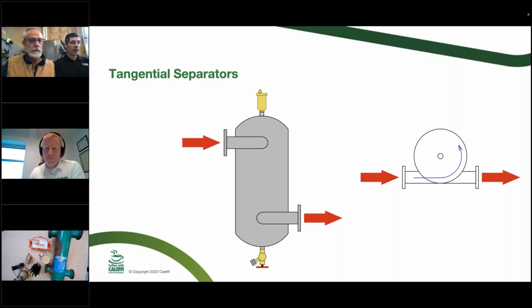So another category in commercial systems, generally big flange systems, would be a tangential separator. This is something that works really well to separate the flow as it goes through. It kind of goes through in a big vortex, and it's going to bring the air to the center and right up to the top. The caveat is that it needs a very specific flow rate. So if you have an ECM pump that might be between 2 and 200 GPM or something like that, you're going to separate air really well at the design conditions, but not as well if you're just sneaking by at a slower velocity, not as many GPM. You're just going to go diagonal, kind of lazy across the center of this.